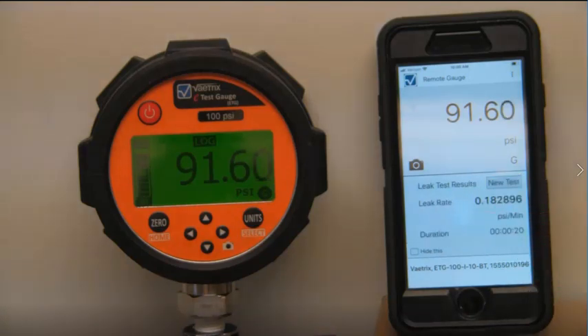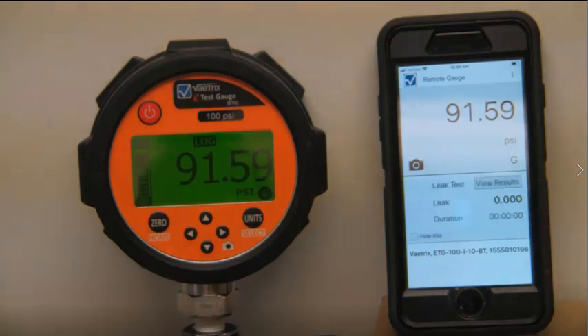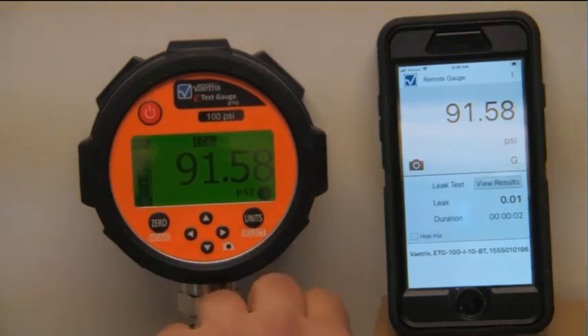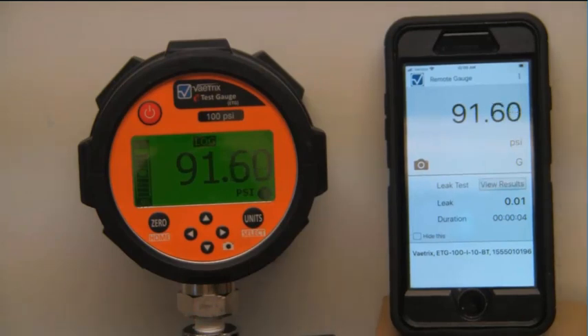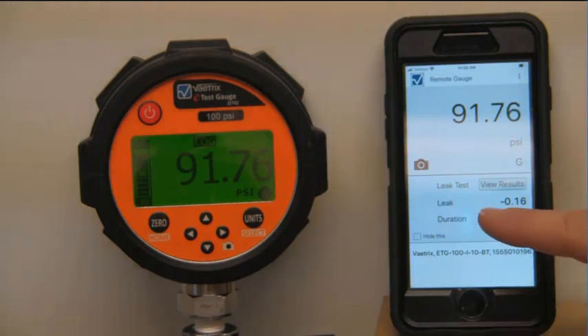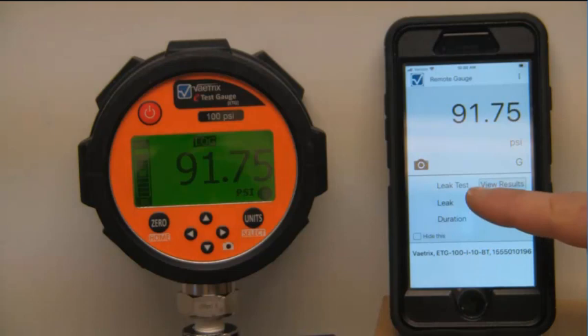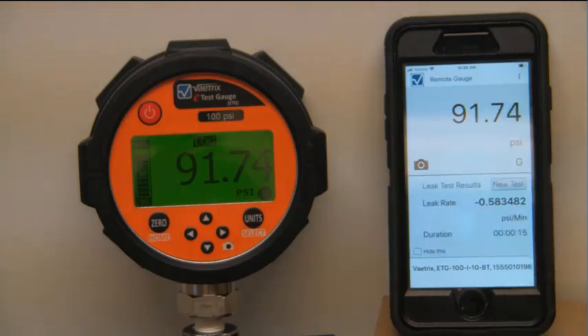So we had a leak rate of 0.182 psi per minute. I can do a new test. I can increase the pressure. So now we actually do not have a leak. We are fighting that leak based on the increase in pressure. I can view the results after 15 seconds. And it is a negative number.